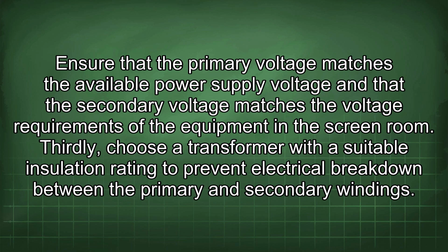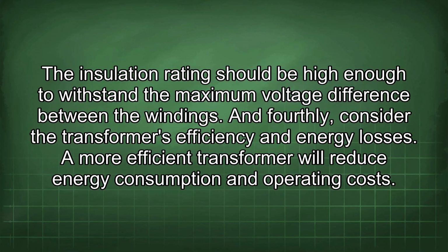Thirdly, choose a transformer with a suitable insulation rating to prevent electrical breakdown between the primary and secondary windings. The insulation rating should be high enough to withstand the maximum voltage difference between the windings. And fourthly, consider the transformer's efficiency and energy losses. A more efficient transformer will reduce energy consumption and operating costs.